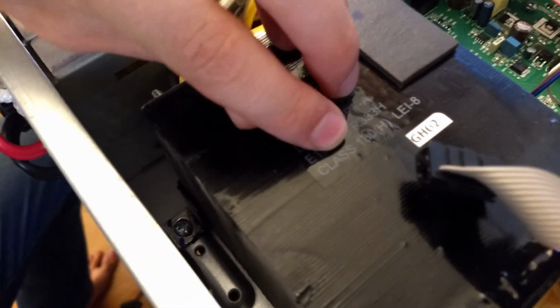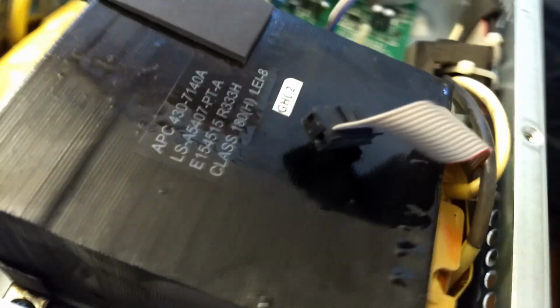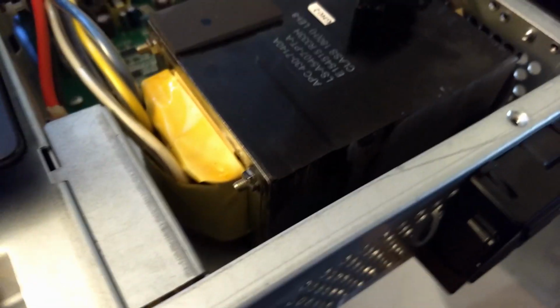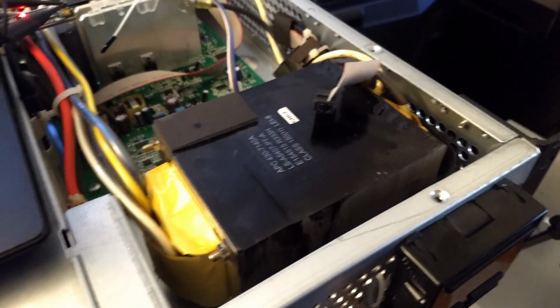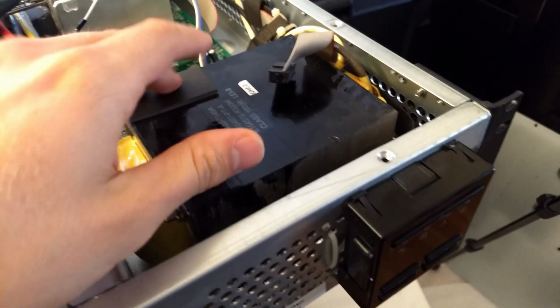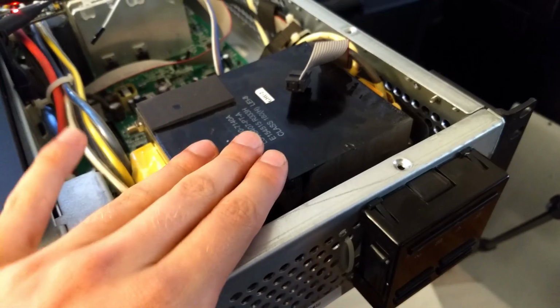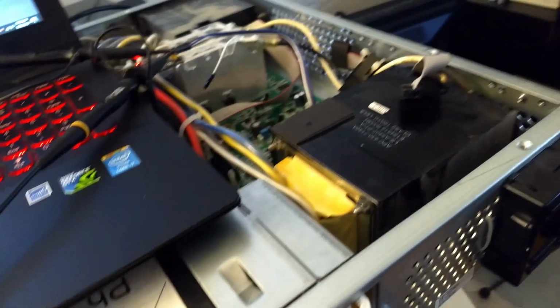And so these are actually rated here. Let me come around. This class 180H means that these are rated up to 180 degrees Celsius. So they can get really, really hot by pretty much anybody's standards. And apparently you only need to leave about a 30 degrees Celsius margin for internal hotspots. So you can measure a case temperature on this guy of 150 degrees Celsius and everything is working happily.